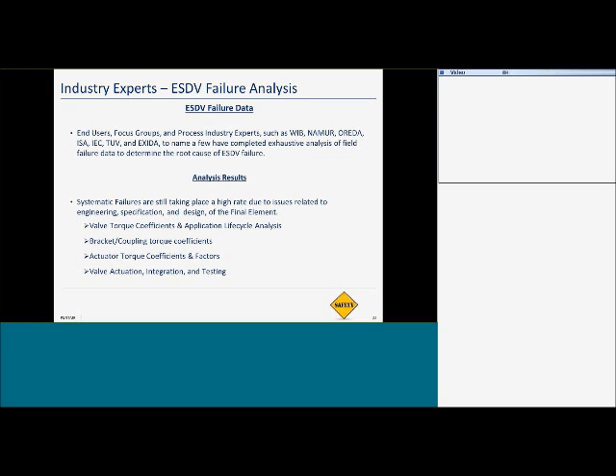And what they found is at the bottom of this slide, you'll see those 4 points. These are the 4 areas that they found were major areas of concern or areas that had caused failure in the field. And the first one you see is valve torque coefficients and application life cycle analysis. So what they determined here was that there had not been adequate application life cycle analysis done in applying the valve to the process. And so like the example I brought up earlier, sulfur vapor recovery, somebody's specifying a valve into clean hydrogen, and they're putting the same valve into sulfur vapor recovery and experiencing failures. And so they defined this as an area of concern and an area where they need to develop some really new approaches, to make sure that proper life cycle analysis is done on the valve as it's applied to the process.